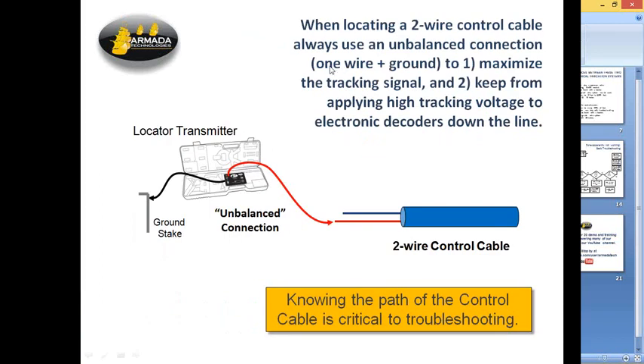And another thing I want to mention in this diagram, when you're locating a two-wire cable, and you have to know the path whether you're working in this kind of system or not. The control cable path is critical to troubleshooting because it leads you to all your application stuff. When you use a locator, couple only to one of the wires in the control cable, and the other lead goes to ground, just like the most common locating application. But we do not recommend that you connect both leads of the locator across the two wires of the control cable. One of the reasons is that a locator, unless it's loaded down, can put out hundreds of volts, and we don't want to damage any decoders that might be sensitive to that in the system, or cause the lightning protection to activate. So you have to be a little careful when you do some locating.